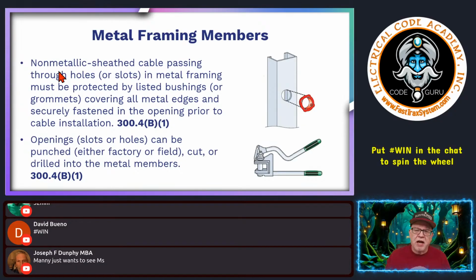So for non-metallic sheathed cable, if you're using wood framing members, okay, it passes through holes or slots. A lot of times they're pre-cut with square slots, or square with rounded corners, still sharp as all get out. If you're using non-metallic sheathed cable in metal framing, they must be protected by a listed bushing or grommet covering all the metal edges and securely fastened, so they click in and don't just pop out. That's in 300.4(B)(1).